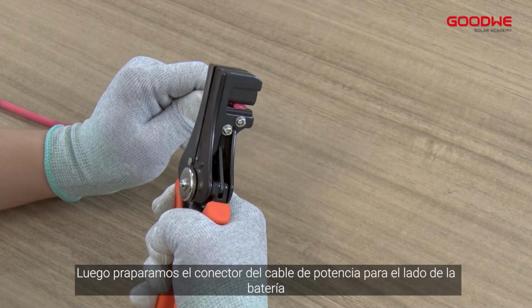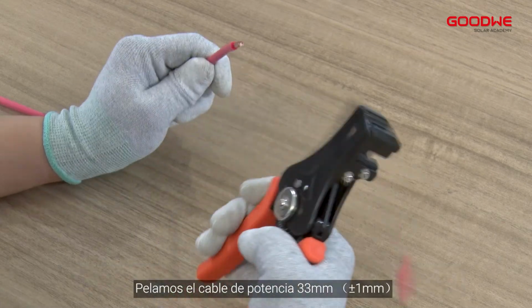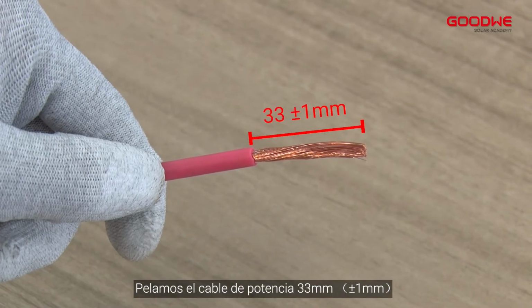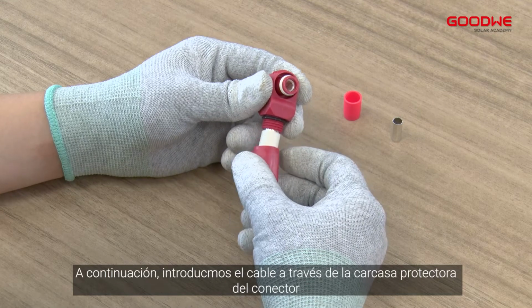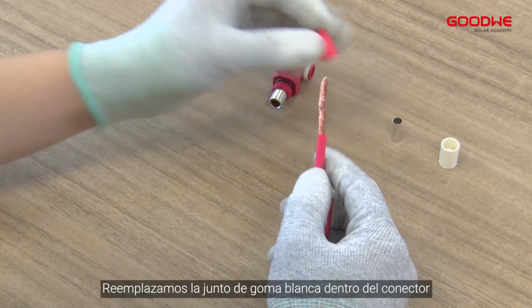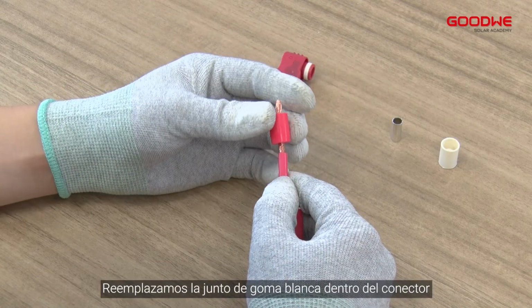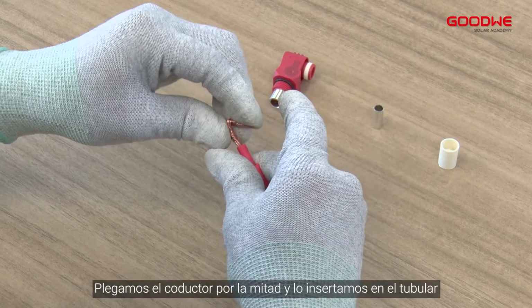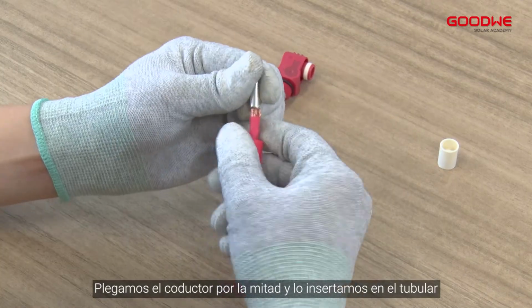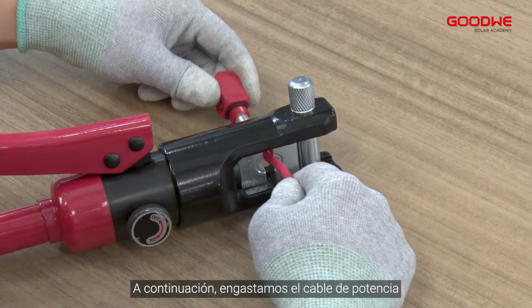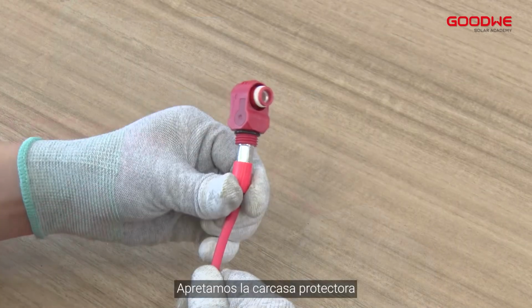Then we make power cable connectors for the battery side. Strip off the wire for 33 mm. Then put the connector nut through the cable. Replace the white seal ring inside the power connector with a red seal ring. Fold the conductor in half and put it into the copper tube. Then crimp the power cable. Tighten the nut.